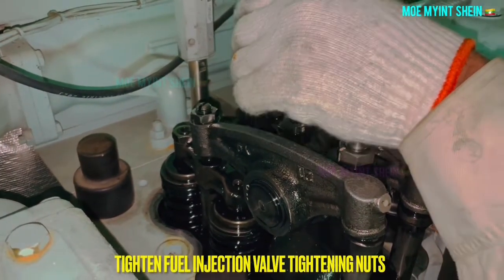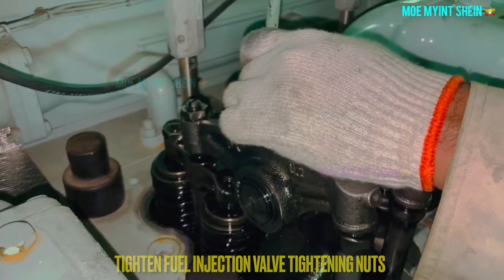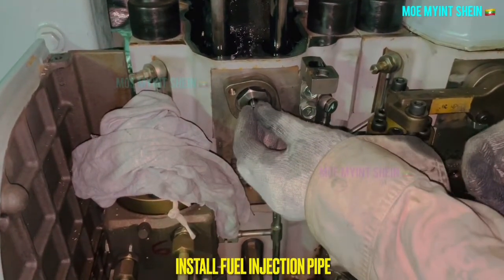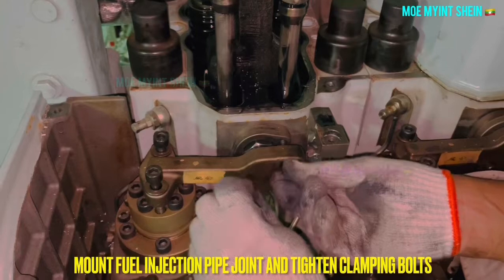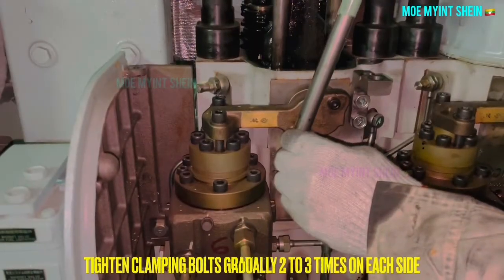At last, tighten the fuel injection valve tightening nuts. Install the injection pipe. Mount the fuel injection pipe joint and tighten the clamping bolts. Tighten the clamping bolts gradually two to three times on each side of the pipe joint.